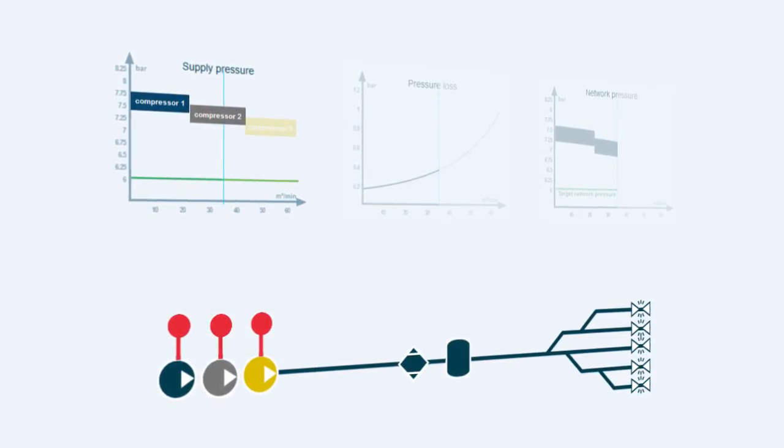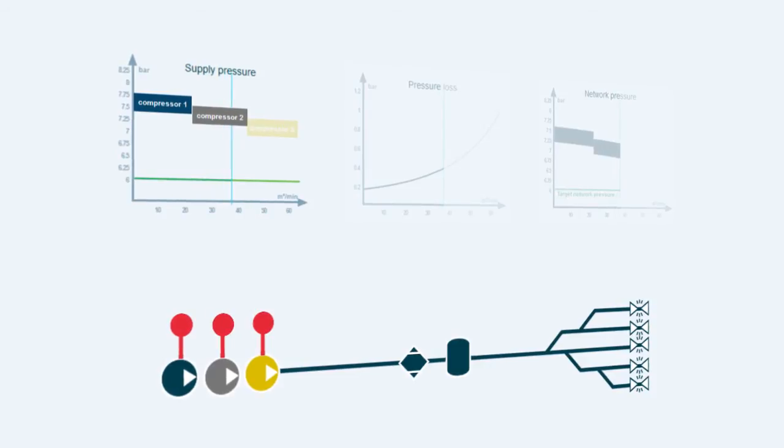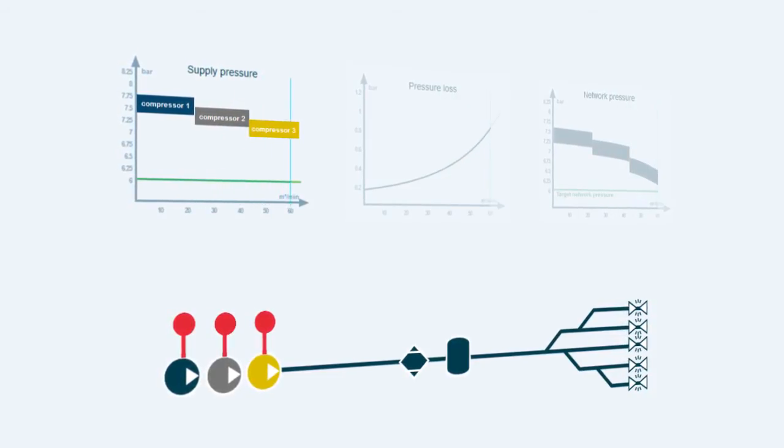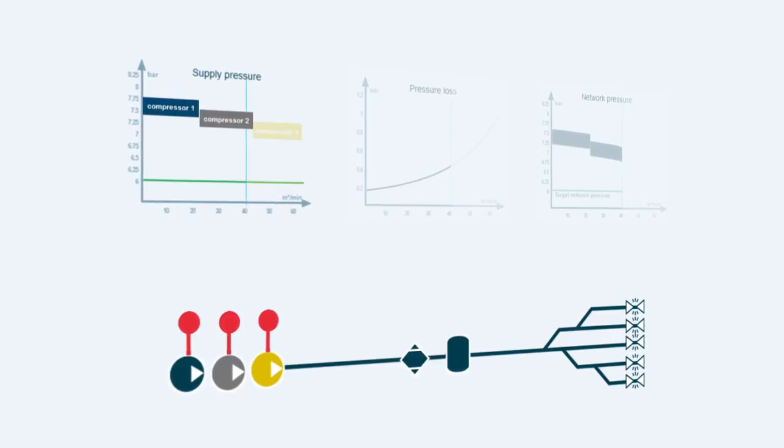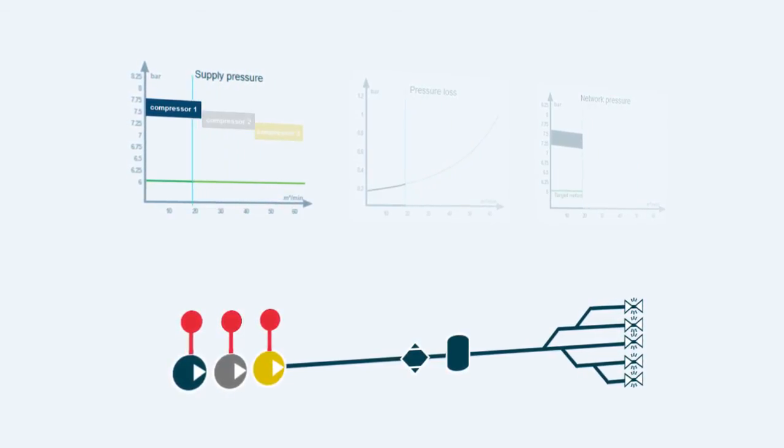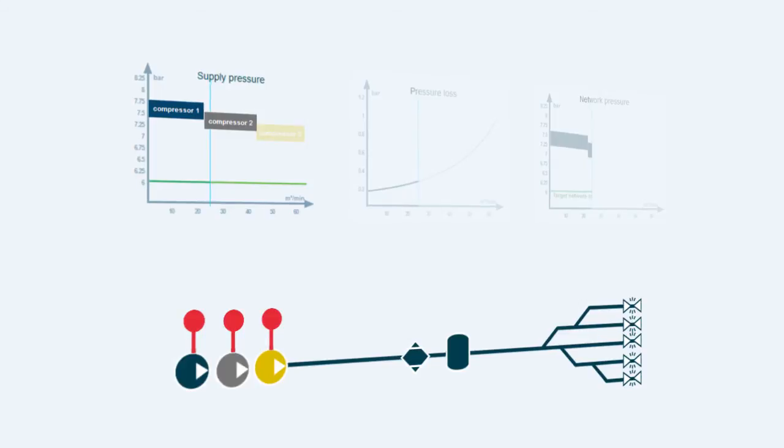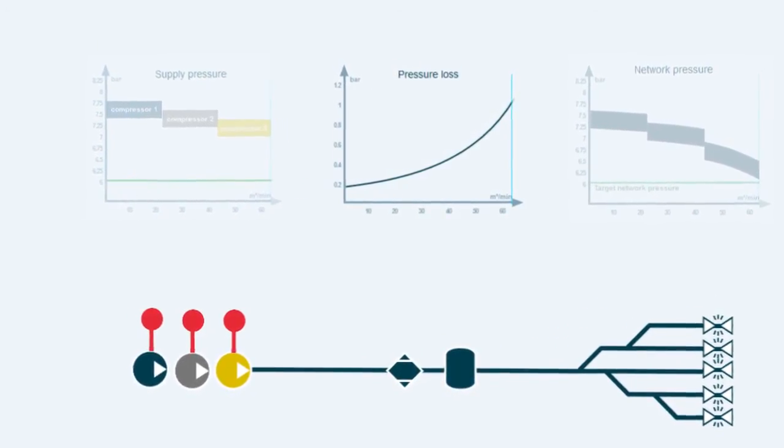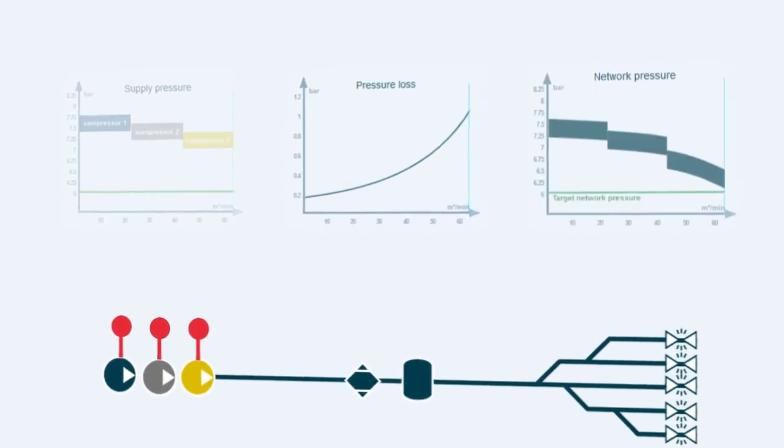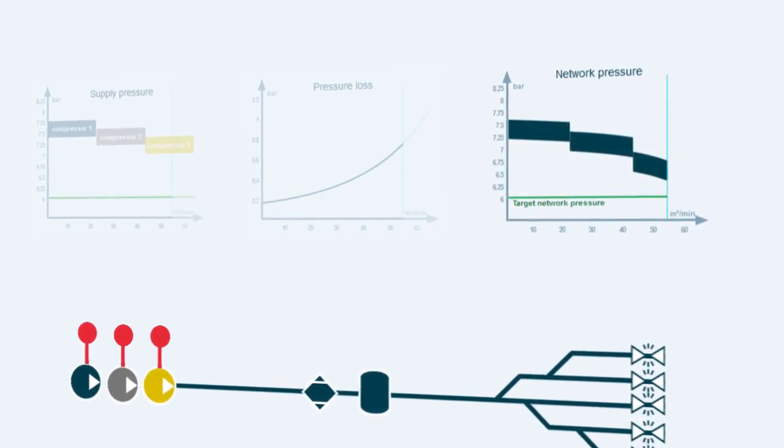At maximum consumption, the output of all three compressors is needed. The result is that the pressure level in the compressor room is high at low consumption, and drops as air consumption increases. Since the air treatment and the pipe work cause further pressure losses, the pressure fluctuation at the consumption point is accentuated.